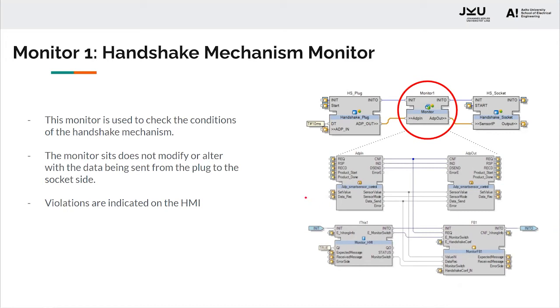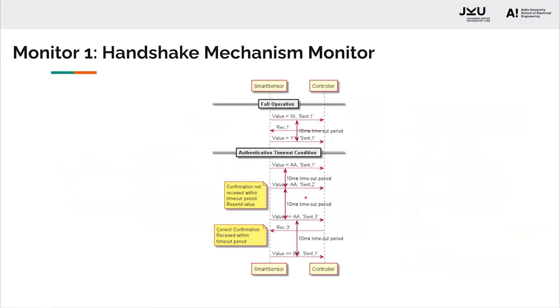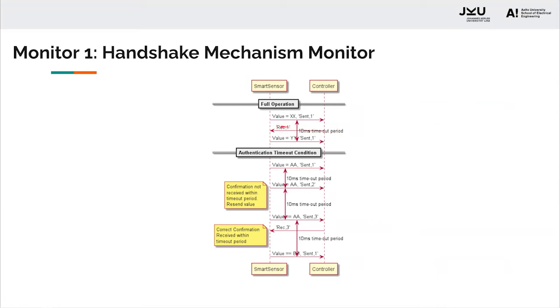Let's look at the handshake mechanism. This handshake mechanism was used to verify the messages sent from the smart sensor to the controller. For example, the smart sensor sends value XX and also adds message sent comma one. As soon as that is received by the controller, it sends back confirmation called receive comma one. This confirmation should be received within a predefined timeout period. Otherwise, the handshake mechanism would assume that the message hasn't reached and would resend the value.